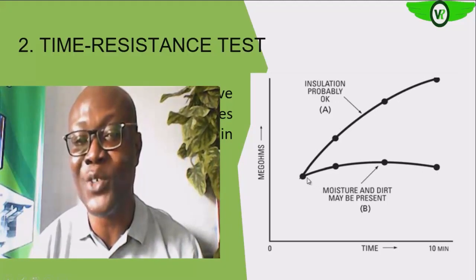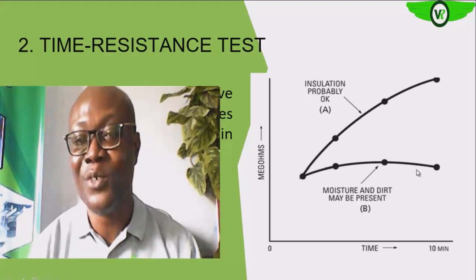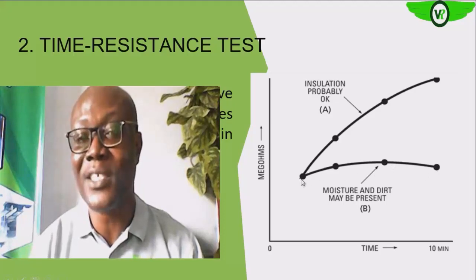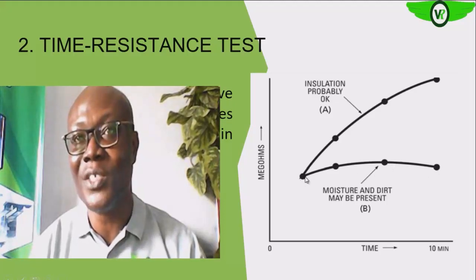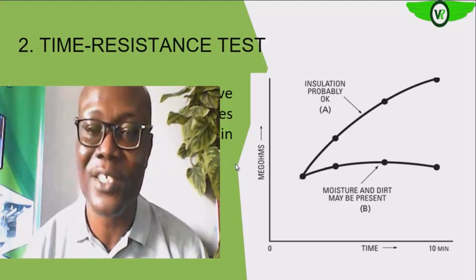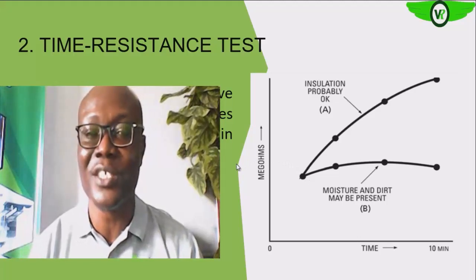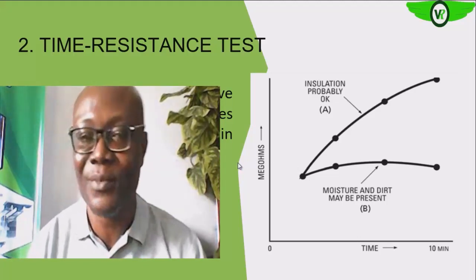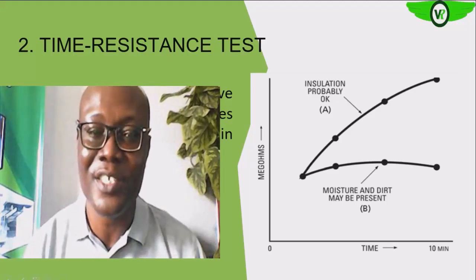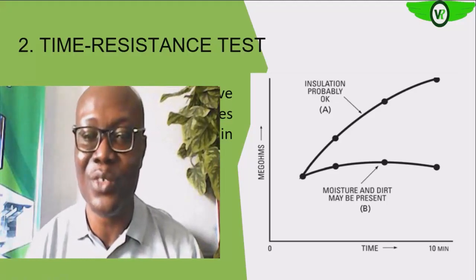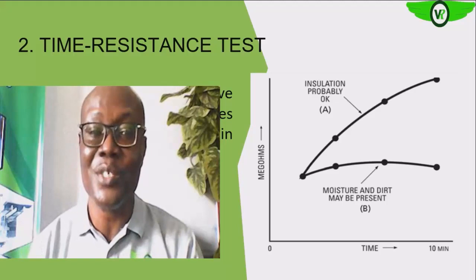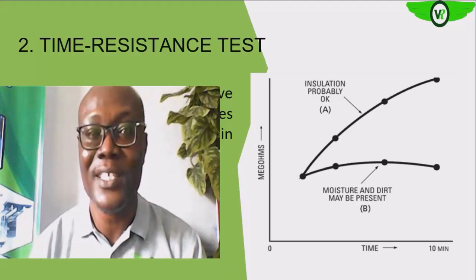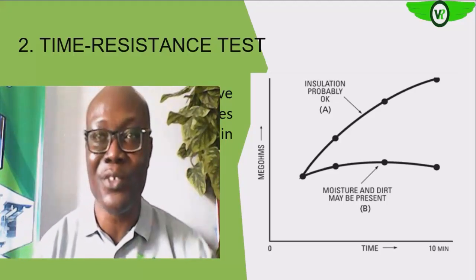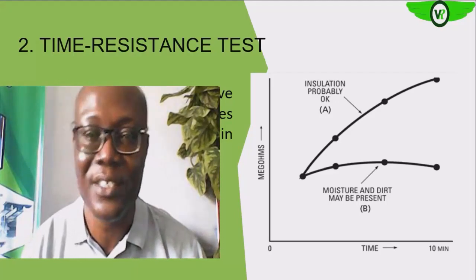So here you may have a ratio of 1 or 1 point something, which is low. That shows that maybe moisture or dirt has been trapped within the winding or within the insulation itself, that is compromising the insulation resistance, or that may eventually cause the insulation resistance to deteriorate. So this shows the beauty of this time resistance test compared to the spot reading tests.